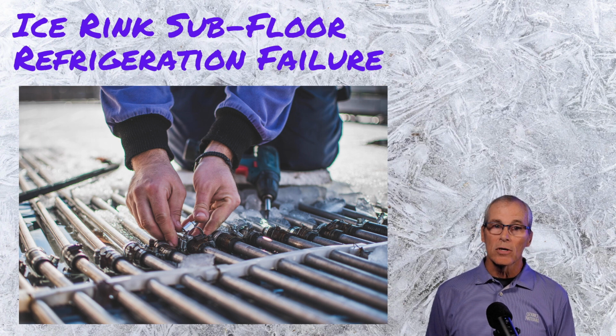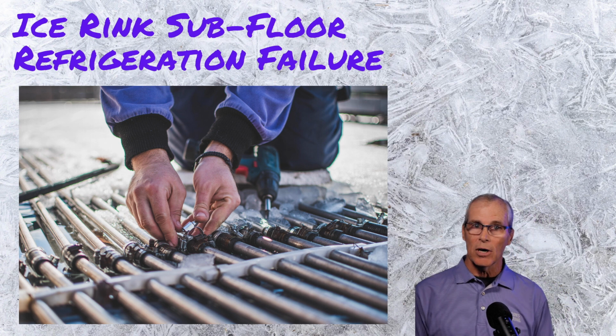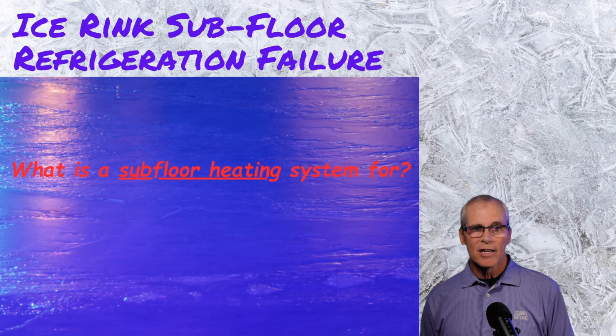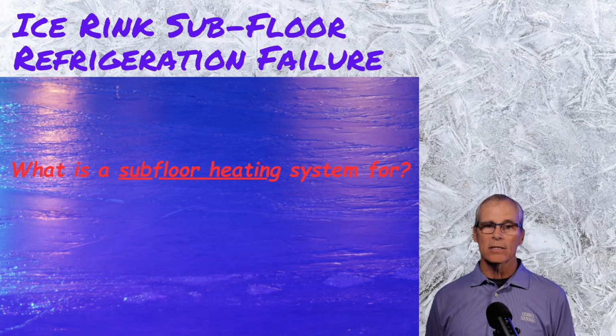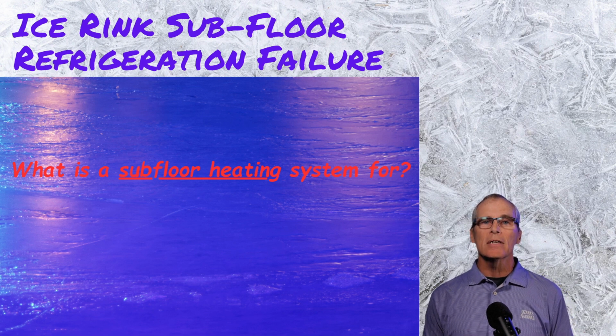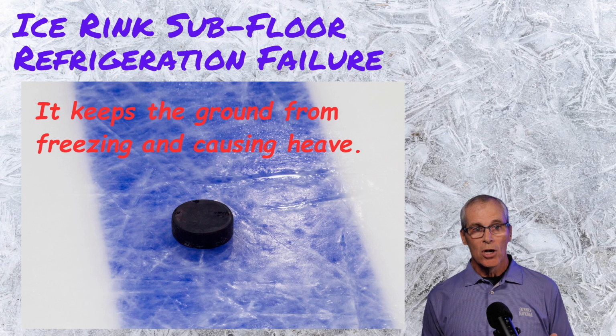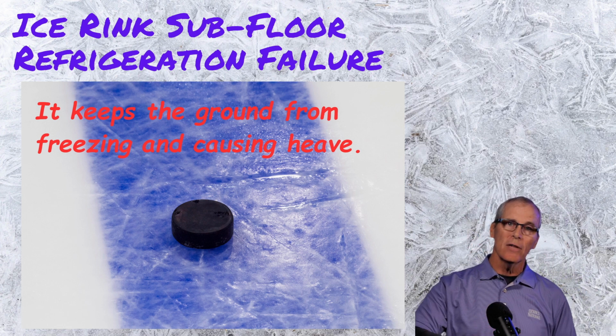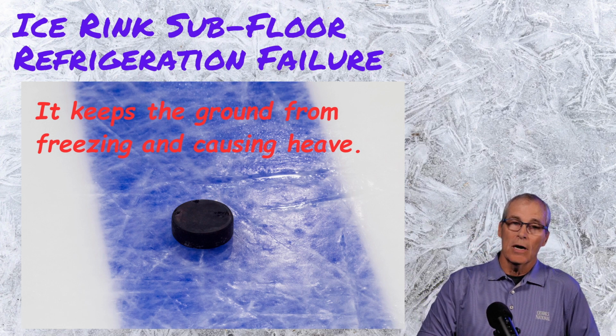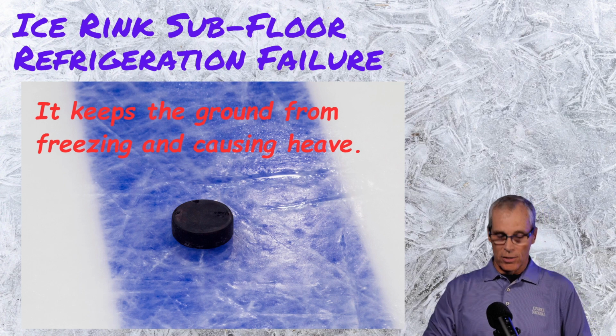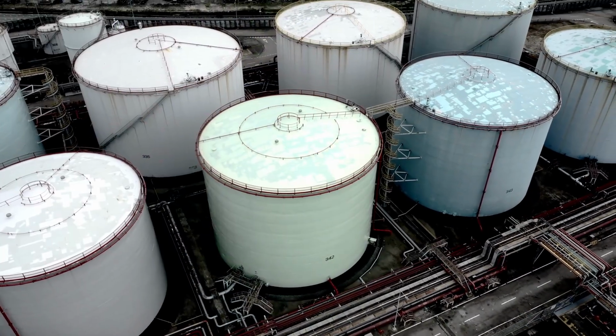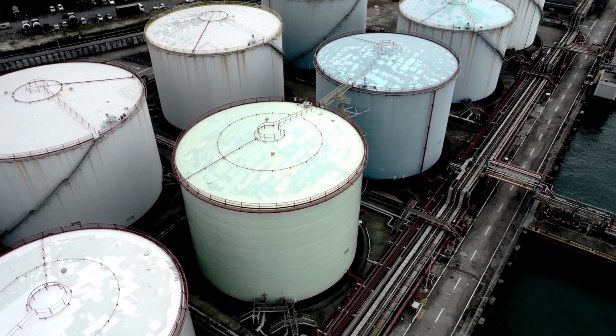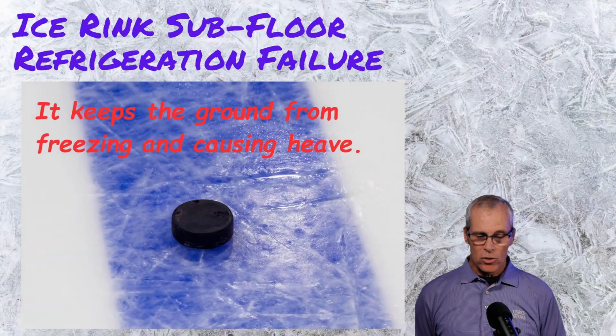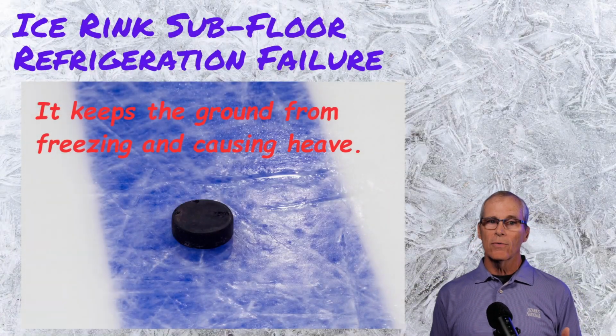Before the concrete is poured, there's a network of cooling pipes and heating pipes. Yes, heating pipes in an ice rink. We'll talk about that. Okay, so what is a subfloor heating system for? It's basically to keep the ground from freezing. So when you build this ice rink and you set it, if it's directly on the ground, eventually the ground will freeze. You see this with LNG tanks. They're either built 3 feet off the ground, or they have a lot of insulation beneath them. Same principle. We can't freeze the ground, or we'll heave it and we'll move that tank. So it keeps the ground from freezing.